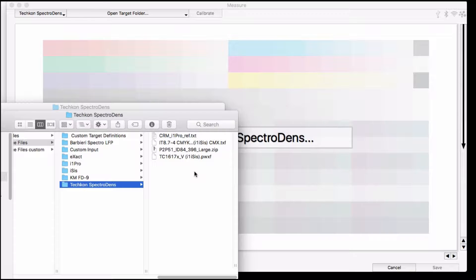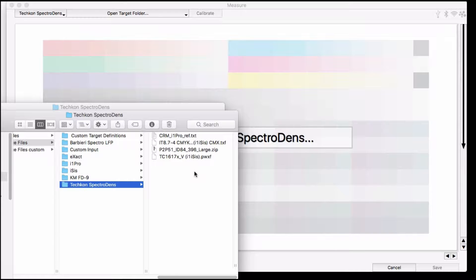If you already have a target definition file for a different instrument, you can likely use that with the SpectroDens and it should work just fine. One of the great new features of our measurement tool is that it can use reference files from different manufacturers, even sources different from the tool you're using.